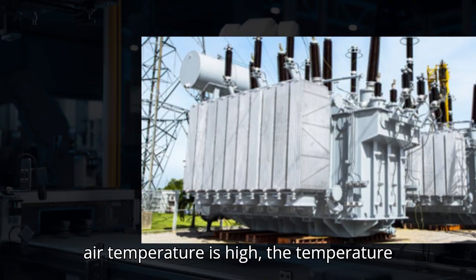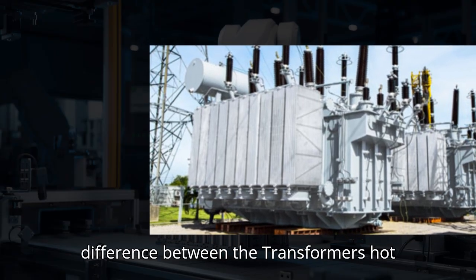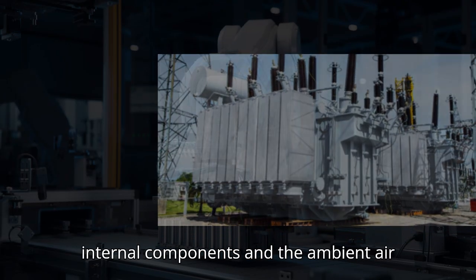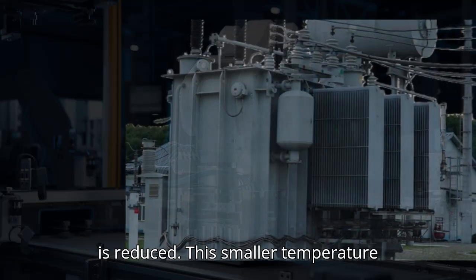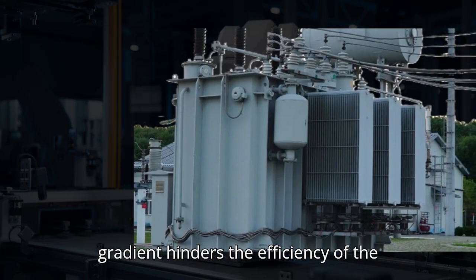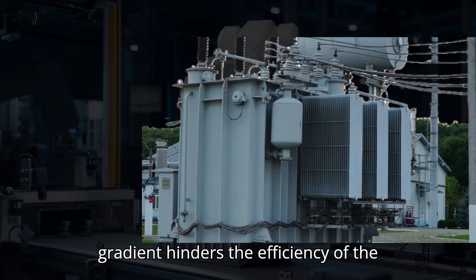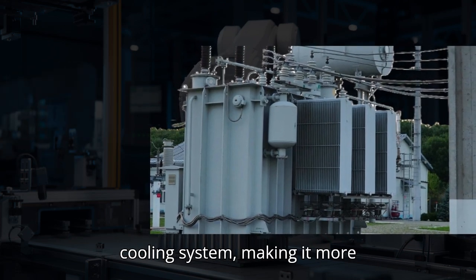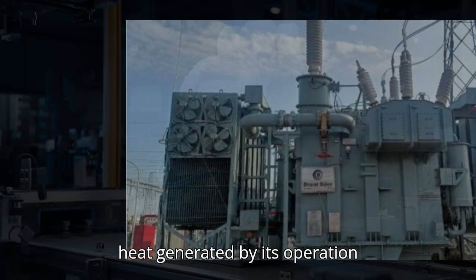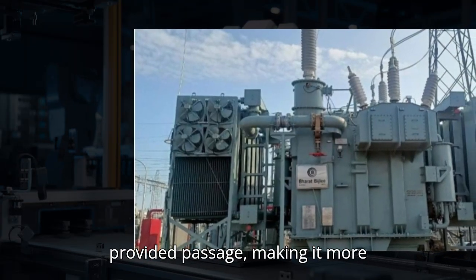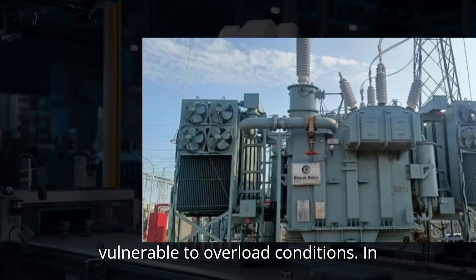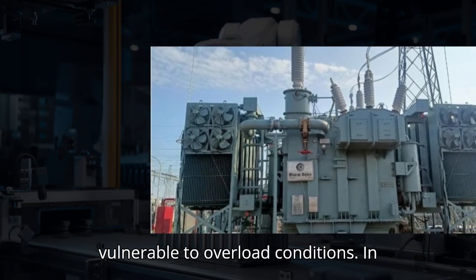When the surrounding air temperature is high, the temperature difference between the transformer's hot internal components and the ambient air is reduced. This smaller temperature gradient hinders the efficiency of the cooling system, making it more difficult for the transformer to shed the heat generated by its operation, making it more vulnerable to overload conditions.